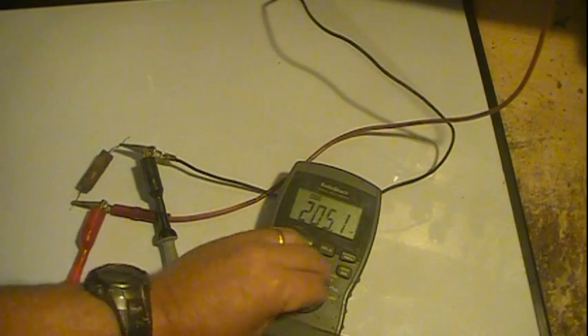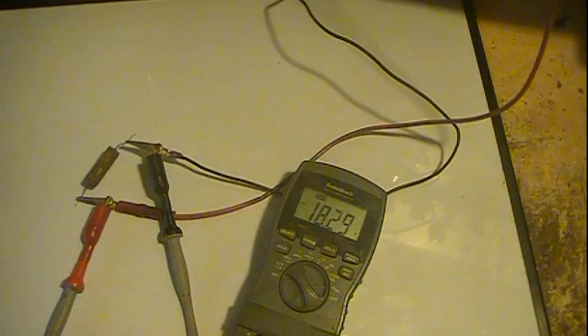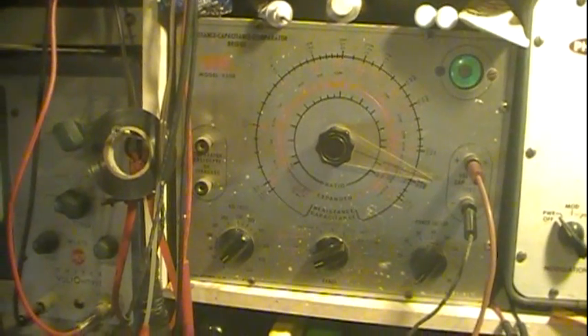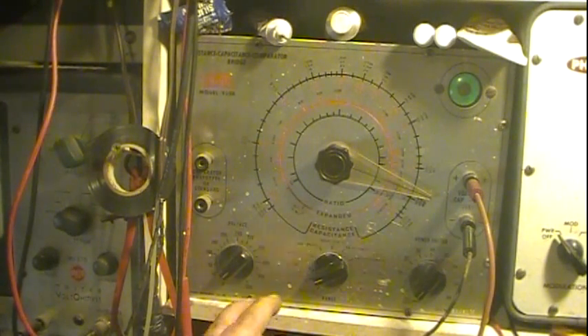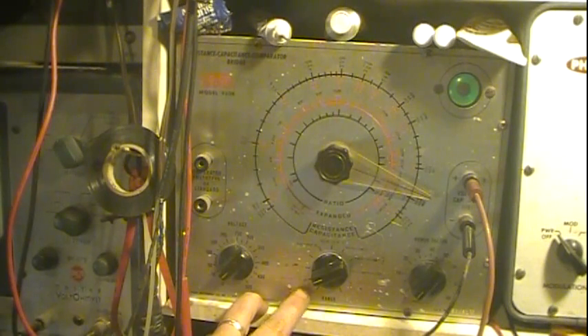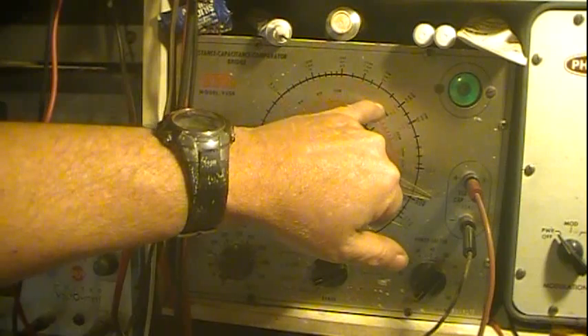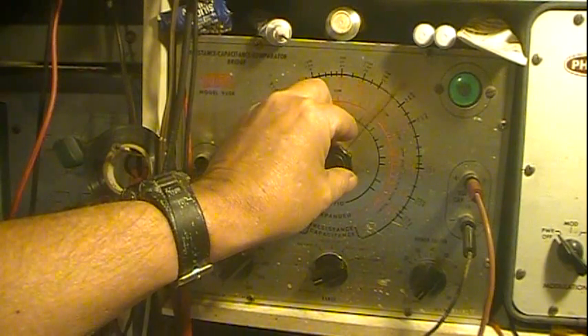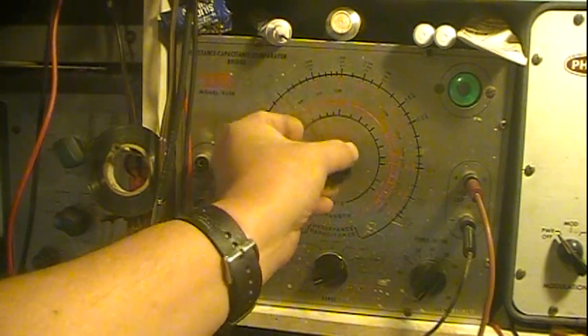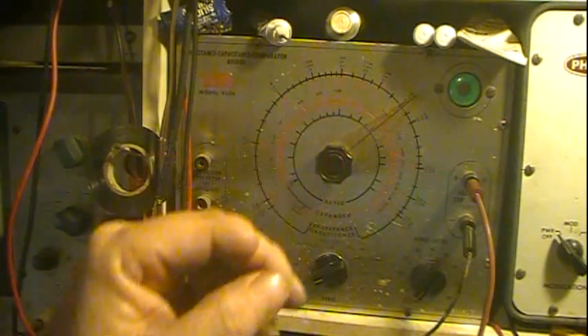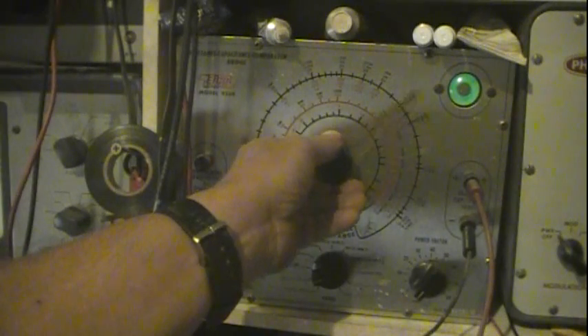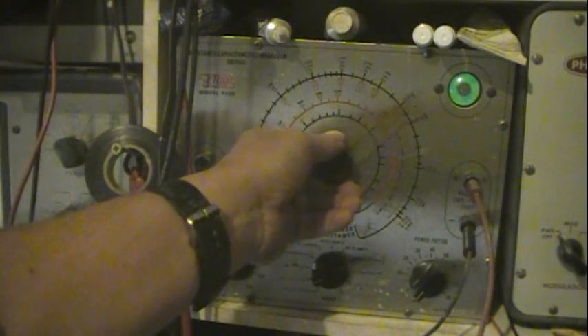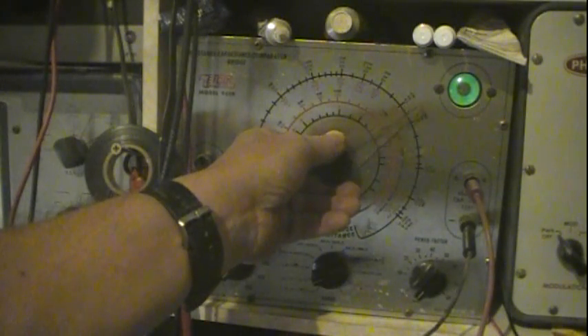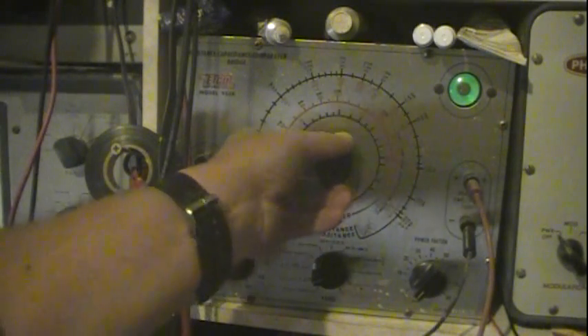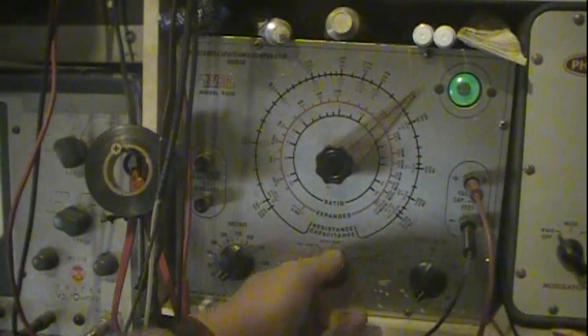So we'll see what we can come up with. Like I said, we're putting 18 volts across it, AC. It's loading the circuit, so it's probably pretty leaky. And let's see if we can get a read on it. We're set on the 0.001 to 0.5. That's the center markings, red markings here. So 0.02 should be up in there someplace. And we're not getting virtually nothing. It tries to shadow there a little bit, like there's something going on. I don't know if you can see that, which is about double its size. So I would say it's probably pretty leaky.